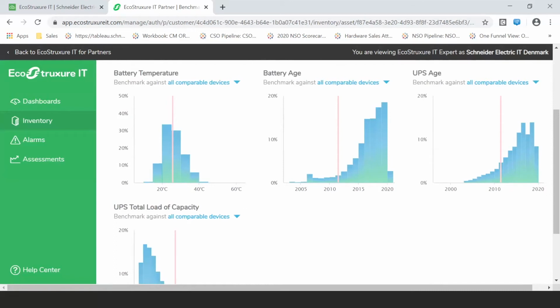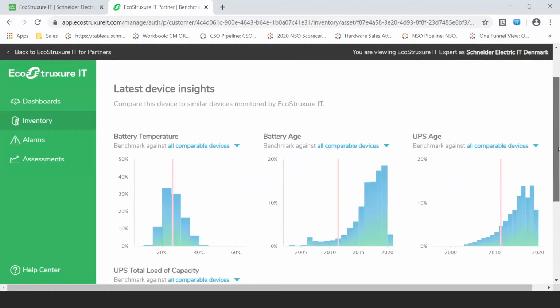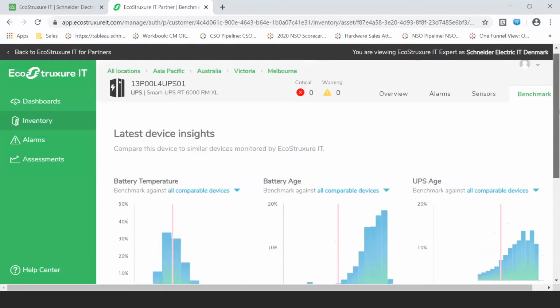It looks like you're pretty warm with the temperature within the IDF that this battery might be sitting in. For the age, this UPS is somewhat old and we can talk about replacement, but there are other units a bit older that are still active. For the most part, the majority of units this old are actually younger than the unit you have, which validates our suggestion to replace this unit or its internal battery. From a UPS perspective, we'd look at the UPS's age itself. This is all critical information to keeping your mission critical gear up and running by managing UPSs correctly.